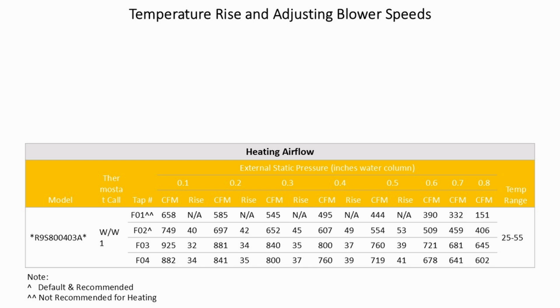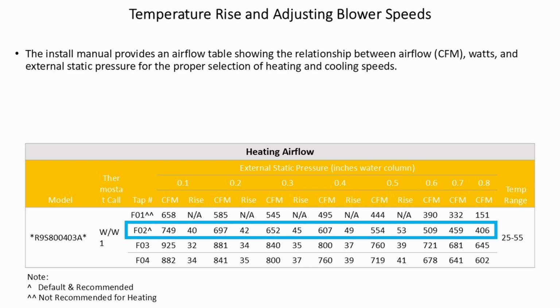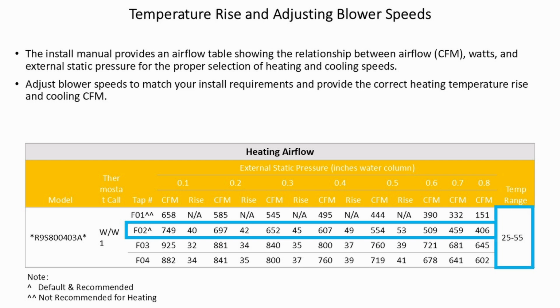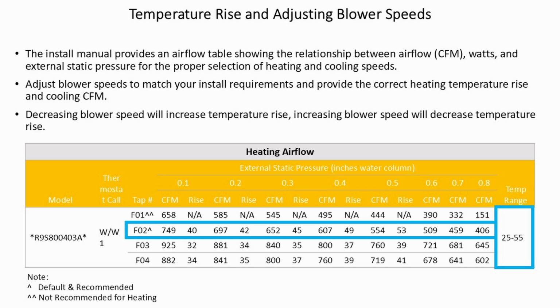Temperature rise and adjusting blower speeds. The installation manual provides an airflow table showing the relationship between airflow in CFM, watts, and external static pressure for the proper selection of heating and cooling speeds. Adjust the blower speed to match your installation requirements and provide the correct heating temperature rise and cooling CFM. Decreasing the blower speed will increase temperature rise. Increasing the blower speed will decrease temperature rise.